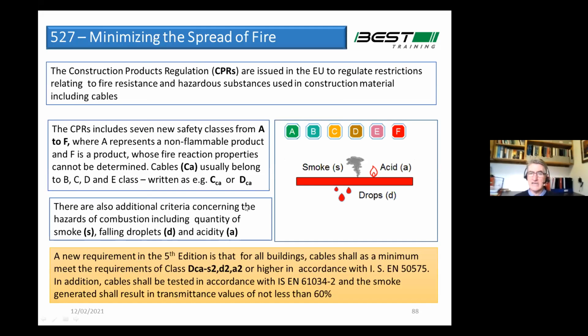Another important part in chapter 7 of chapter 5 is minimizing the spread of fire. So I mentioned earlier on the CPRs. These are the construction product regulations, and they have now brought out a classification system for designating the fire performance of cables. So in Ireland, we've chosen that the minimum performance now is DCA S2D2. In other words, you need to do better than that. That's the absolute minimum that will be accepted now. So for example, a cable worse than that would be an ECA, which would be a kind of PVC cable. They're no longer acceptable. So it's basically in the realm of, I suppose, LSF or LSZH type cables.